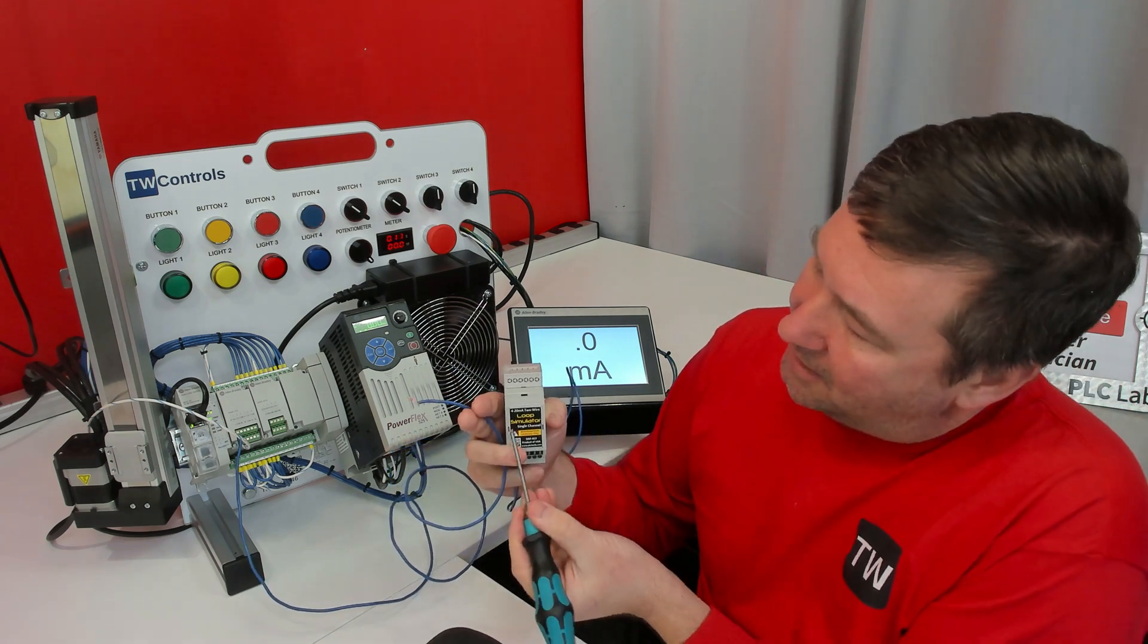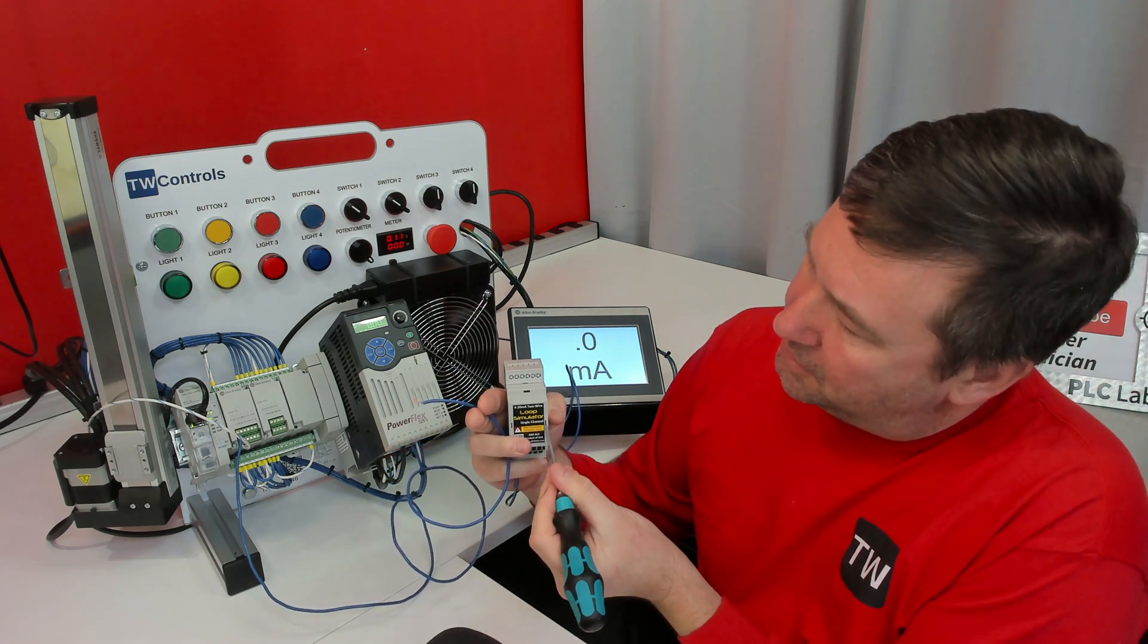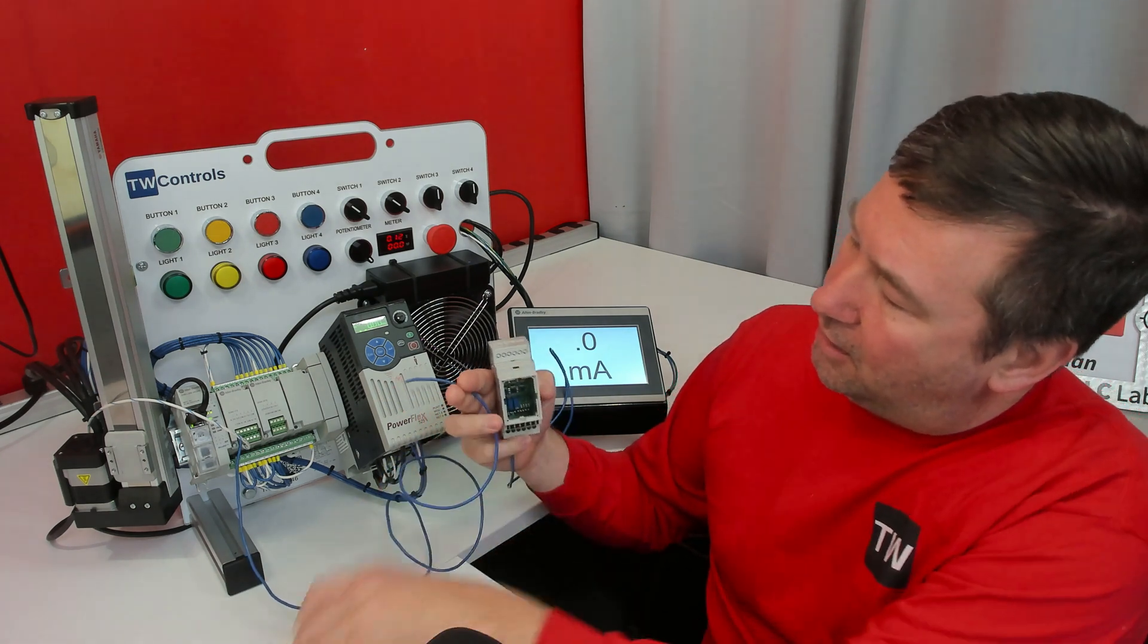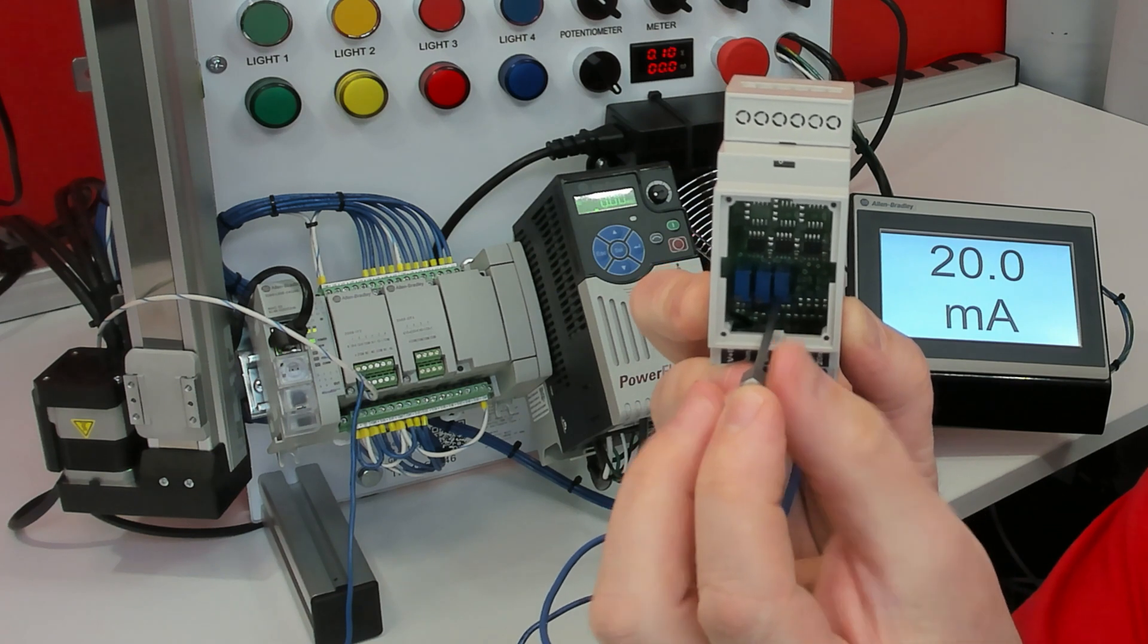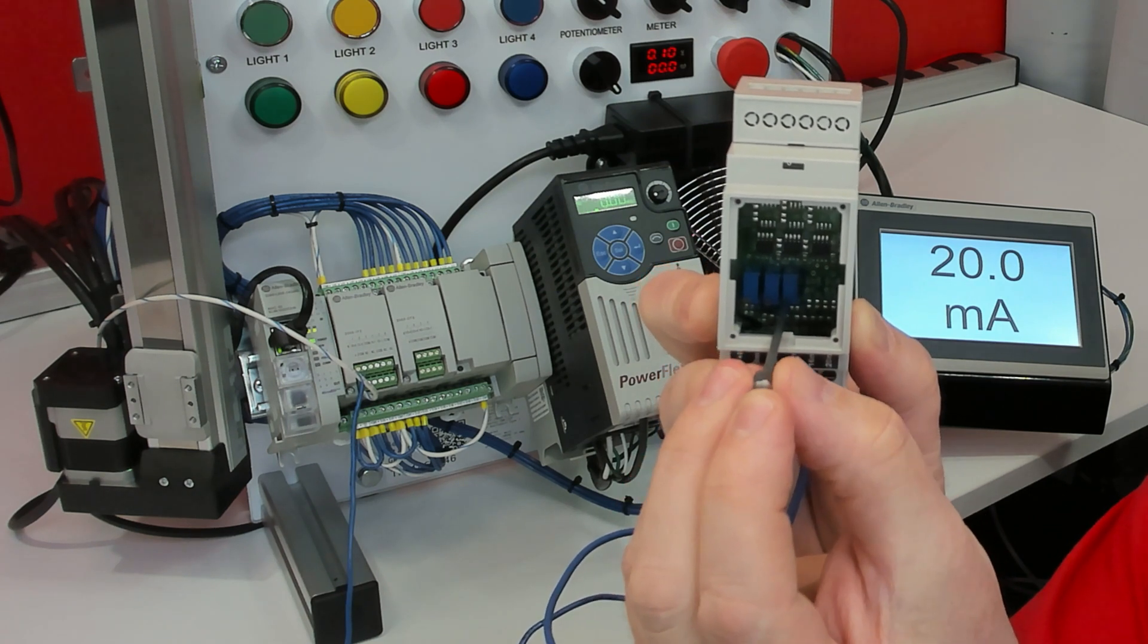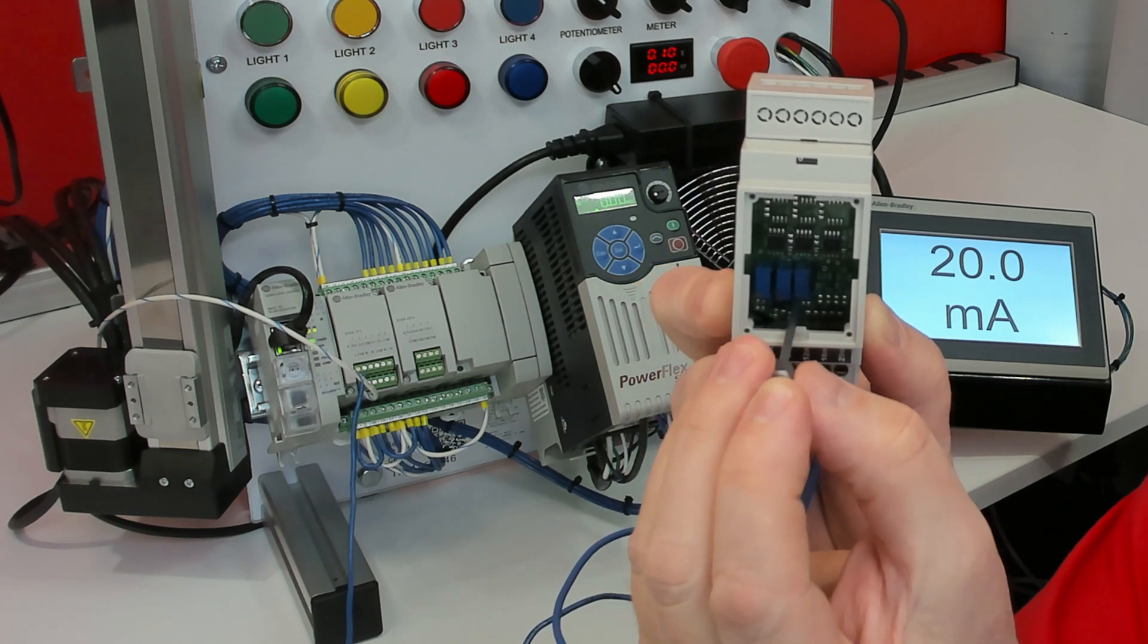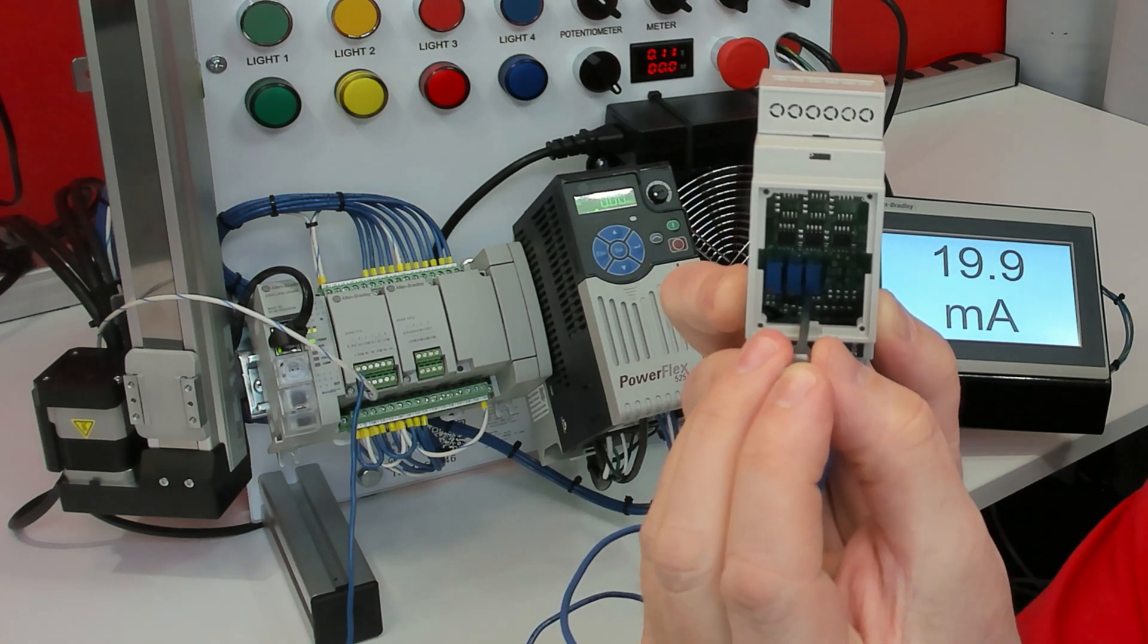There's a slot on both sides of the cover and if you gently put a screwdriver in there, then the cover will come off. And inside of here, you're going to see three trim pots. And if I turn this counterclockwise, then it's going to slowly drop down this milliamp value.